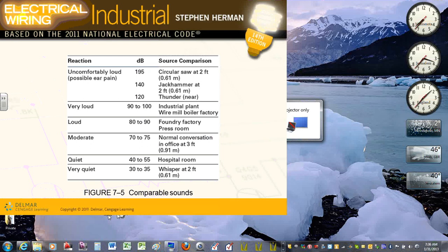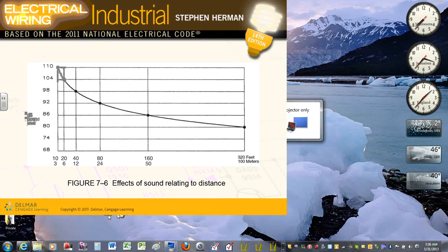There's another, this is important, guys, for two reasons. This curve is important for two reasons, for the ones who are going to be designers. Reason number one is when you design your paging system, you're going to make sure that everybody can hear you, unlike our paging. Did you guys hear the paging system here? Do you hear it? Horrible. Completely, right? Horrible. This is a good example of a badly designed paging system. Voltage drop, probably high in voltage drop, low in volume. So when you design it, you want to make the ambient noise such that everybody can hear. You don't want to blast your ears, but I can't hear. So there's a lot of impedance balancing between them and so forth.